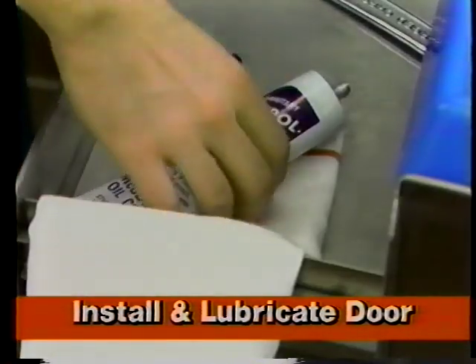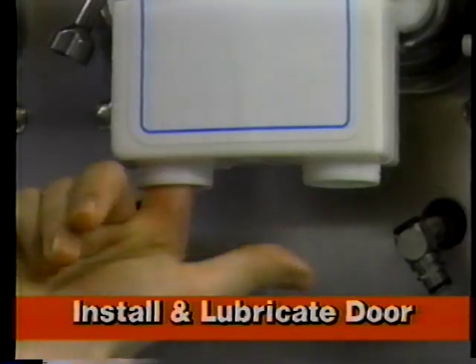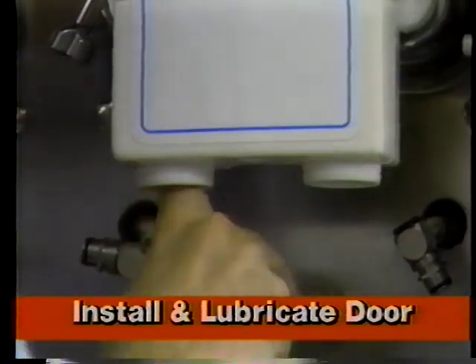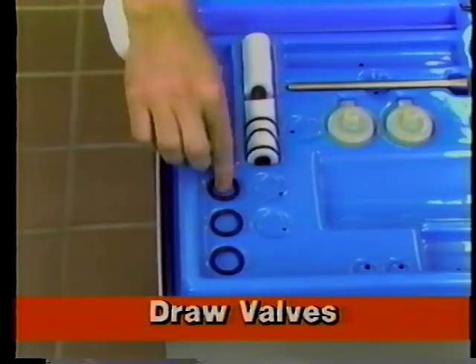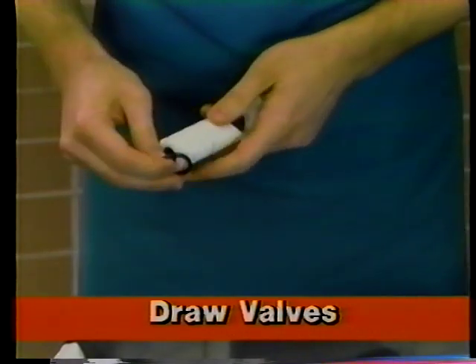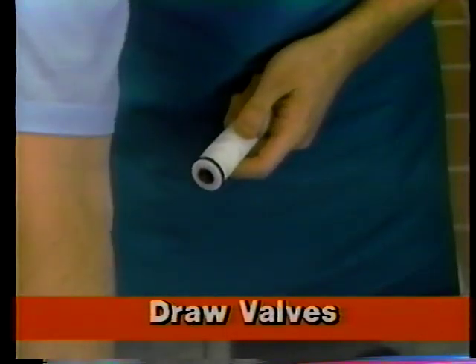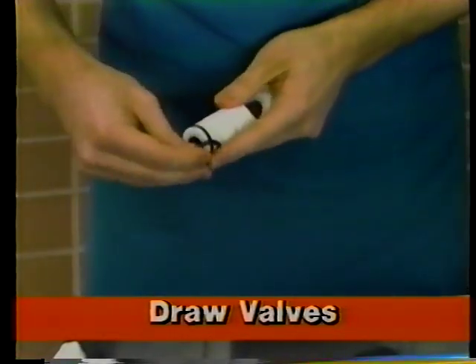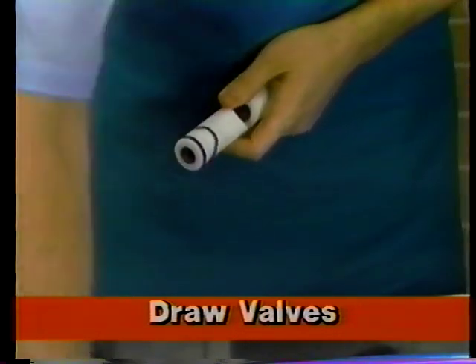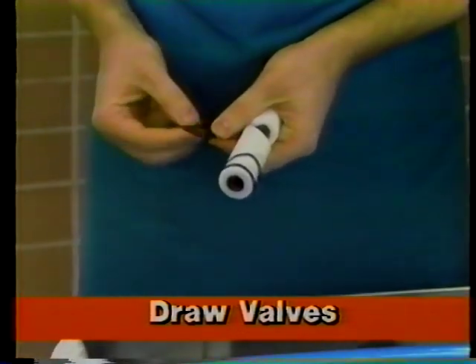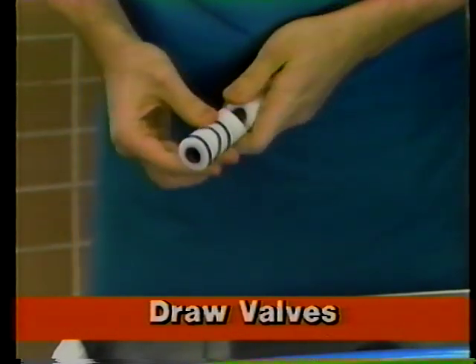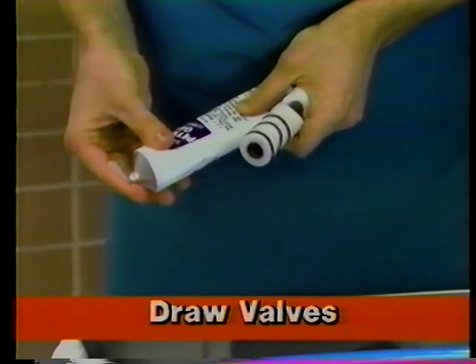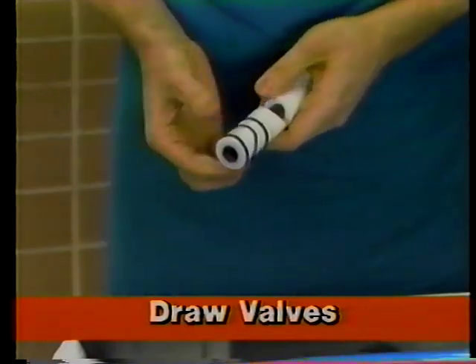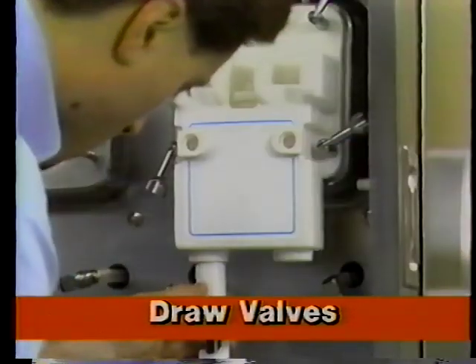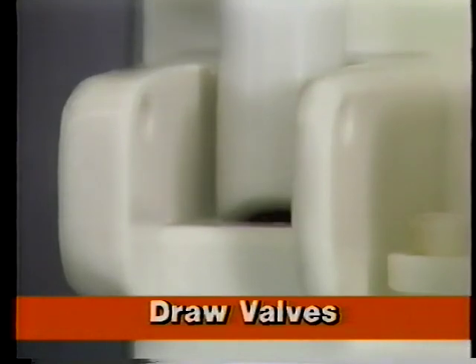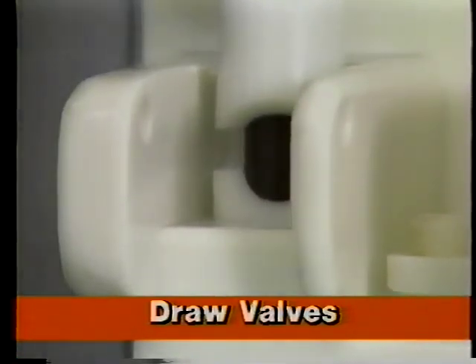Next, you have to lubricate the inside of the spouts in the freezer door, top and bottom, as far in as you can reach with your finger. Now, assemble the draw valves for each spout and install them in the door. There are 2 draw valves for each door and 3 O-rings that go on each valve. Don't forget to check each O-ring for any damage, and then slide the O-rings into the slots on the valve. Then, get some Petrogel on your finger and lubricate all 3 O-rings. Put the valves into the door from the bottom, so the slot in the valve comes out the top of the door and looks like this.